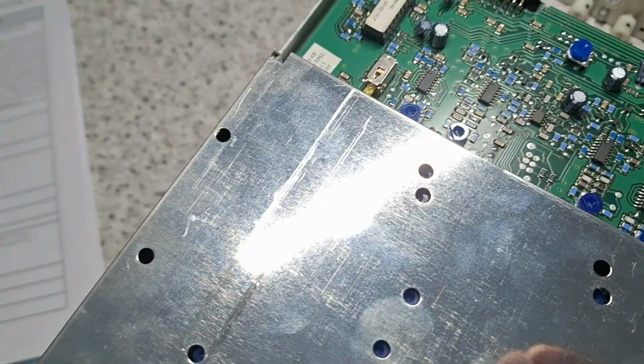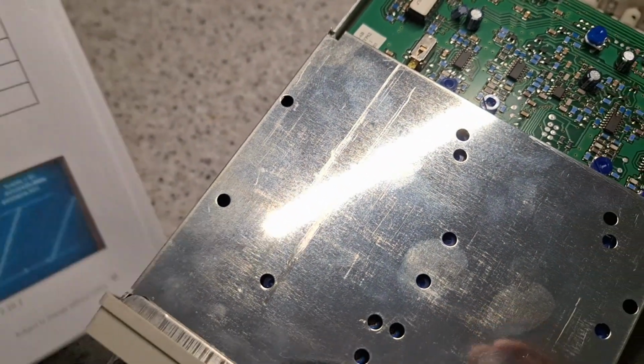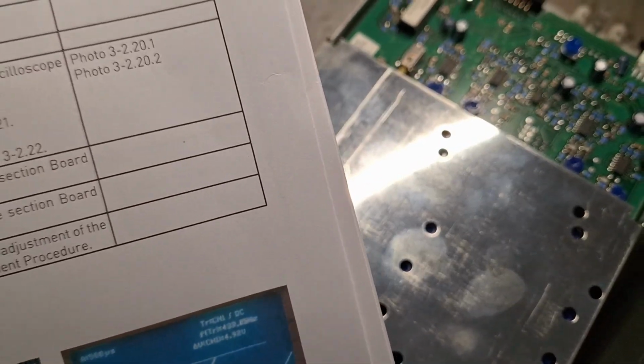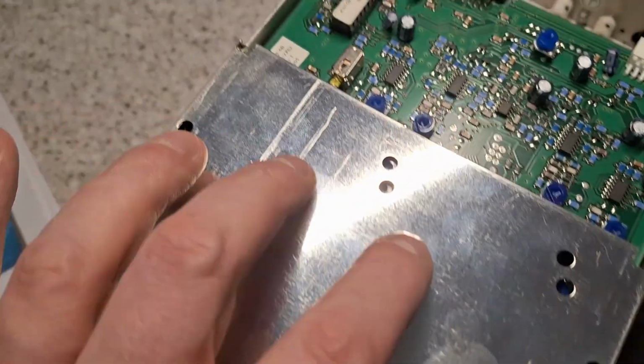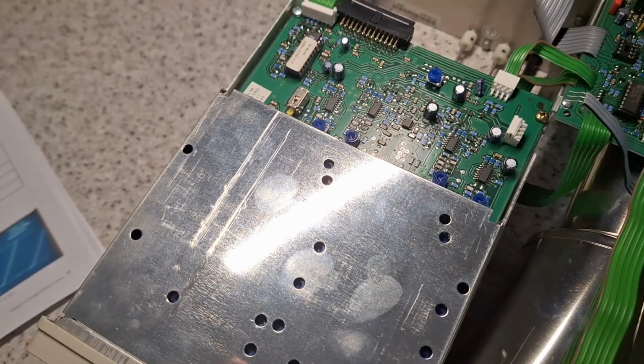I did actually measure voltages on there, there was nothing coming out of it, so it would appear, yeah, that's what the issue is. It's a fault on this YP board, so we'll have to investigate that. Now I think I've found the issue.